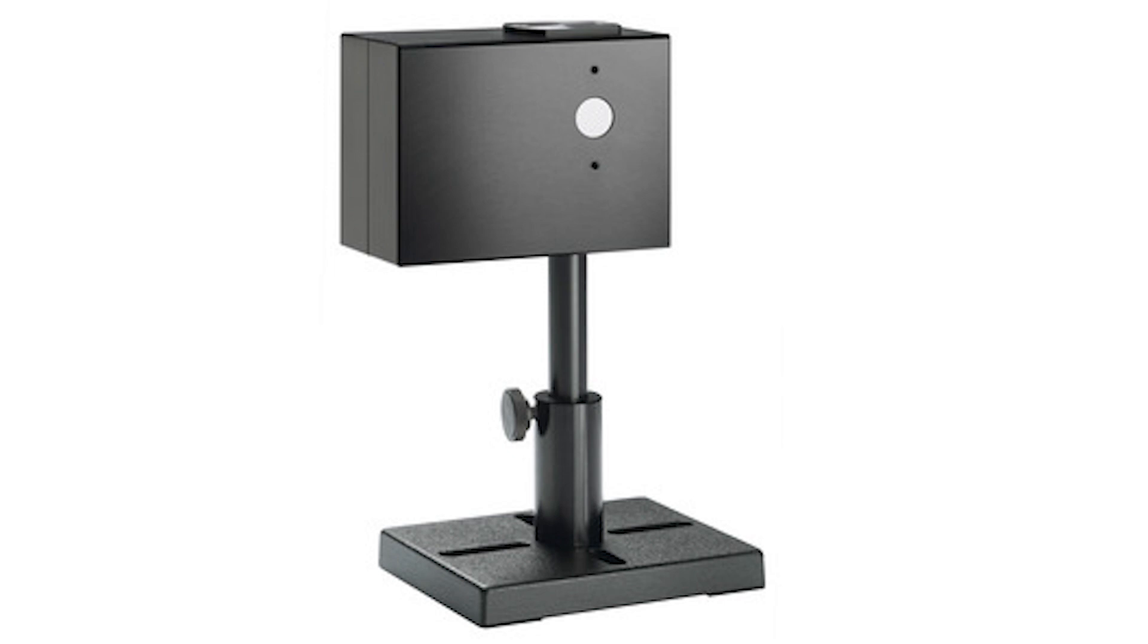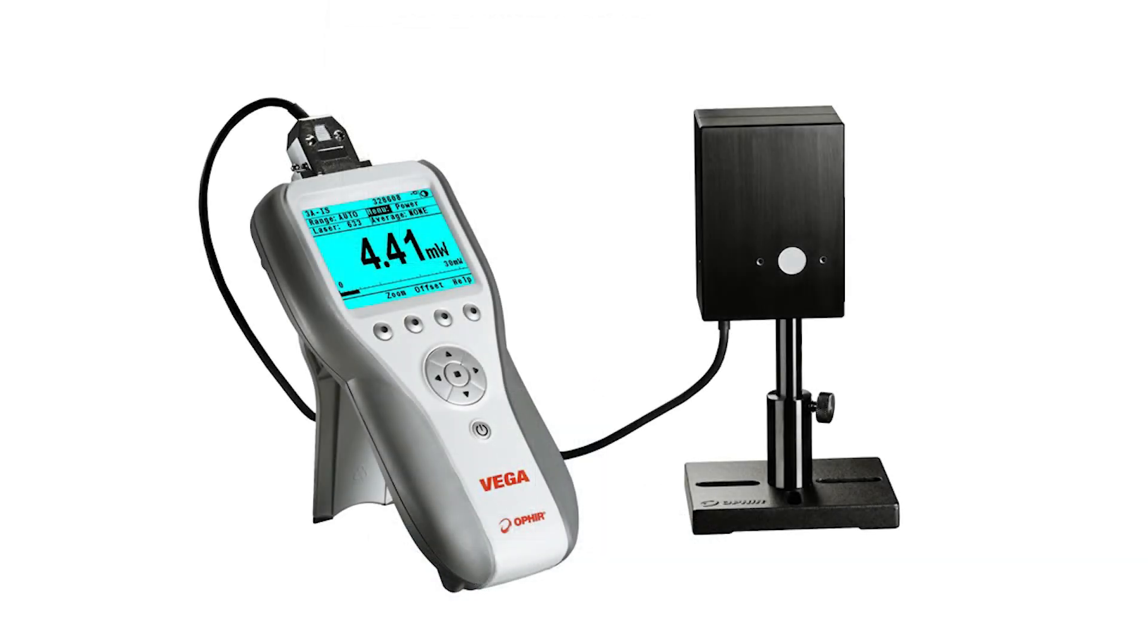The Ophir 3AIS is an integrating sphere sensor consisting of a small 1.6-inch integrating sphere and a built-in photodiode detector. The whole device is calibrated over a wide spectral range and is configured as a standard Ophir smart sensor compatible with any standard Ophir smart meter.